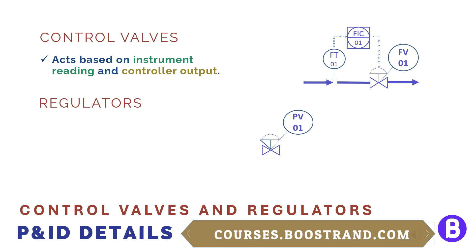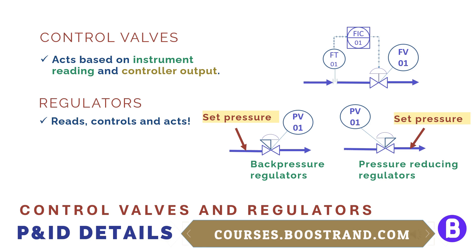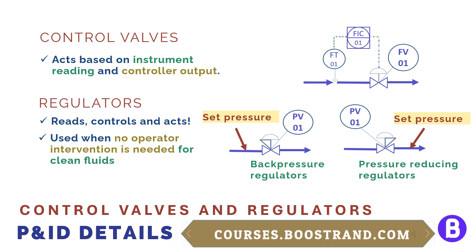We can also use self-regulating valves, which are called PCV. Here we can control the parameter locally from the valve itself — the valve senses the pressure and adjusts its opening. These can be either pressure reducing regulators, which control the downstream pressure, or back pressure regulators. They can only be used in clean fluids and only in applications that need no operator intervention, such as reducing the instrument supply pressure or gas blanketing in vessels or storage tanks.